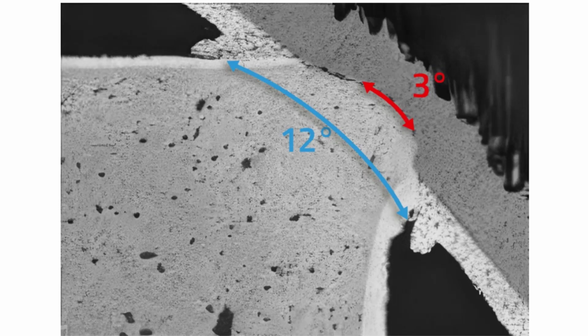Press-fit technology offers several advantages over solder technology. It's particularly adept at handling very thick circuit boards with heavy copper plating. Additionally, it allows for trouble-free two-sided mounting of circuit boards, facilitating compact module designs. With press-fit technology, there's consistent contact between the pin and the copper layer along the entire length of the press-fit zone. This reliability is not assured with soldering, as solder may not fully rise along the entire length of the via, leading to increased transition resistances. Consequently, the long-term reliability and mechanical stability are not as robust as with REDCUBE's press fits.